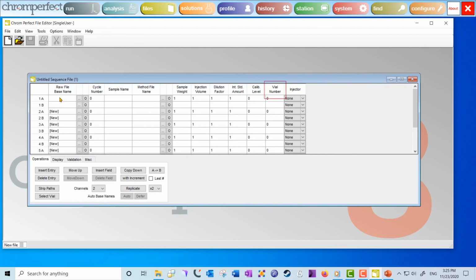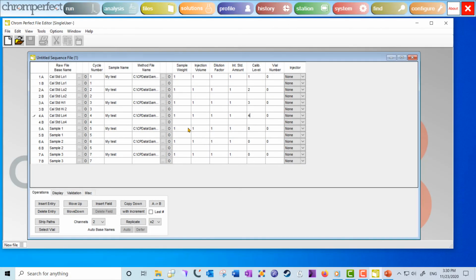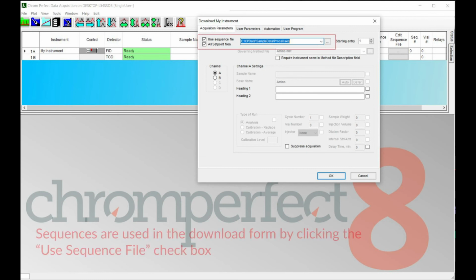If you are using an autosampler, you must supply the vial number as well. The sample name is handy, but not necessary. The 4 numbers do not matter because they support features in the calibration file which are not turned on yet. Also, review the Copy Down and Copy Down with Increment buttons. They can save you time entering data to the sequence table. Review the settings, then save the sequence file. Supply the name mytest.seq or any name you like. You can now use your sequence file to acquire data by clicking the Run button.